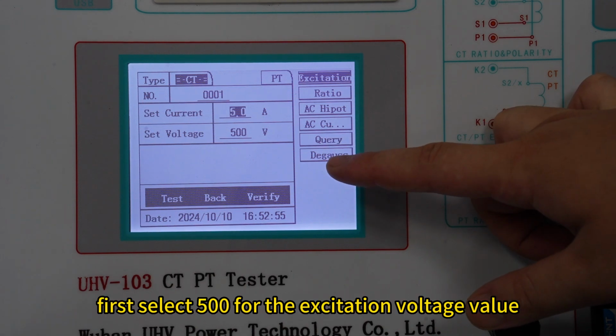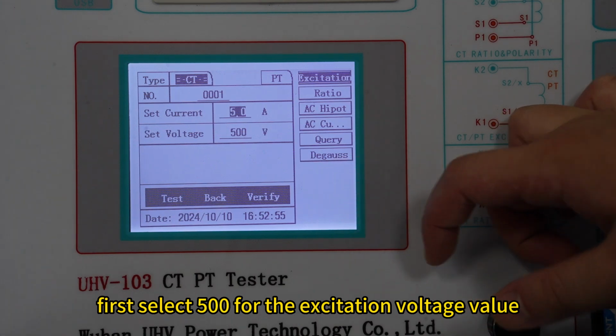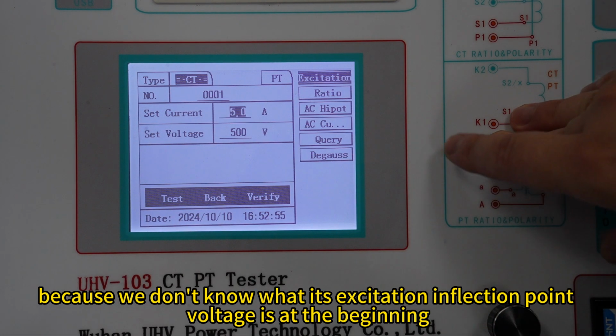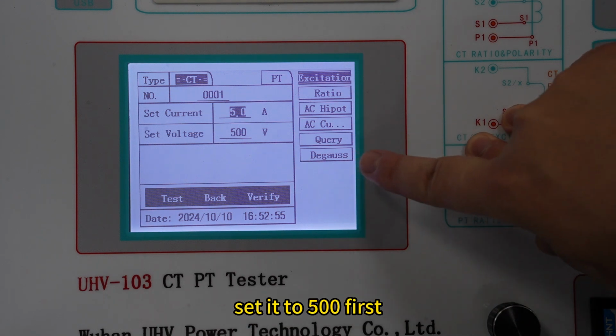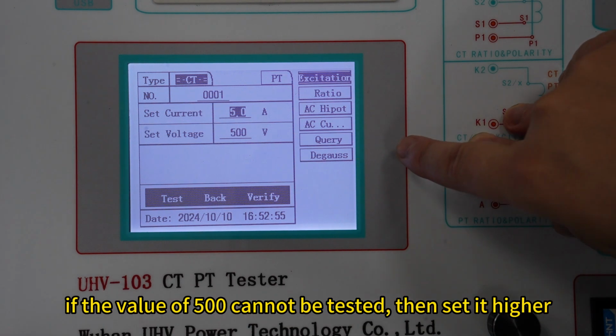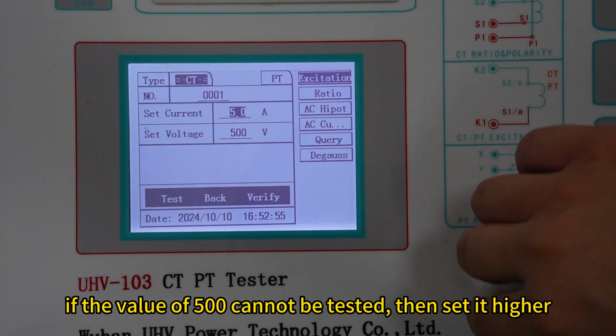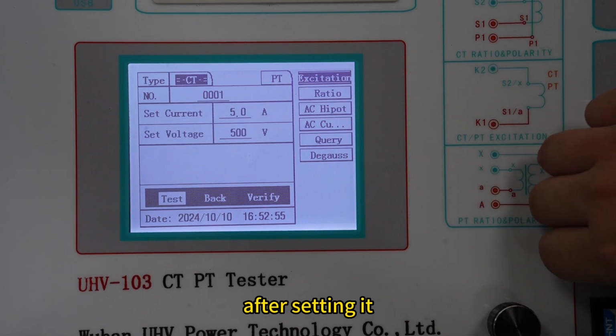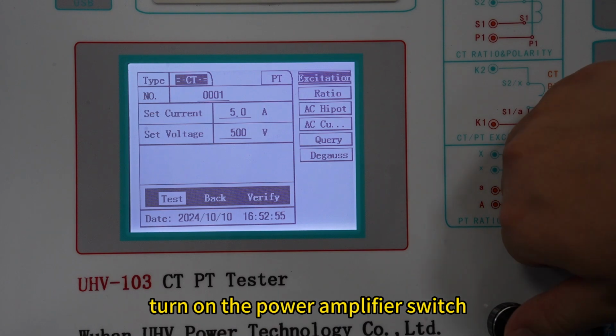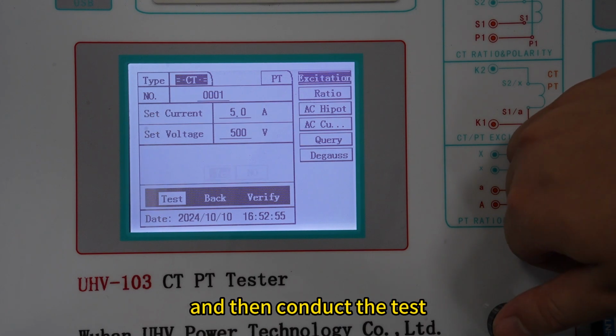First, select 500 for the excitation voltage value. Because we don't know what its excitation inflection point voltage is at the beginning, set it to 500 first. If the value of 500 cannot be tested, then set it higher. After setting it, turn on the power amplifier switch, and then conduct the test.